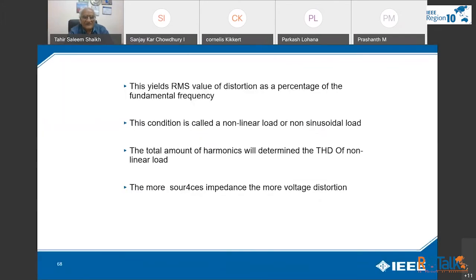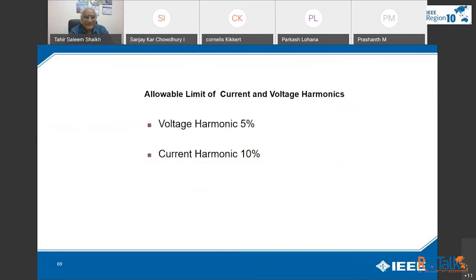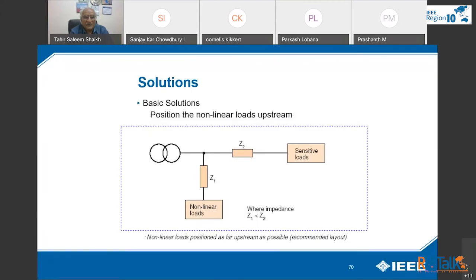This yields the RMS value of distortion as a percentage of the fundamental frequency. This condition is called a non-linear load, a non-sinusoidal load. The total amount of harmonics will determine the THD of the non-linear load. The more the source impedance, the more the voltage distortion. Generally, in general practice, many global multinational companies have set limits for the allowable current and voltage. The voltage harmonics is 5% and current harmonics is 10% as the maximum limit. Otherwise, we have to go for that. So these are some of the basic solutions for that.